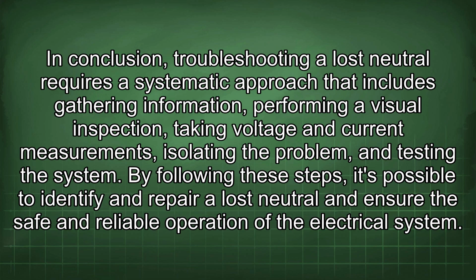Finally, it's important to document the problem, the troubleshooting steps, and the repairs that were made. This information can be used to prevent future occurrences and to support insurance claims. In conclusion, troubleshooting a lost neutral requires a systematic approach that includes gathering information, performing a visual inspection, taking voltage and current measurements, isolating the problem, and testing the system. By following these steps, it's possible to identify and repair a lost neutral and ensure the safe and reliable operation of the electrical system.